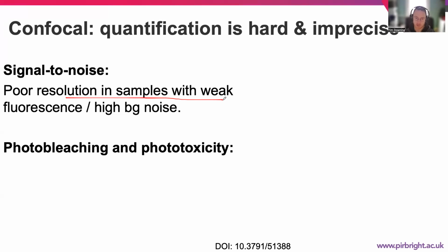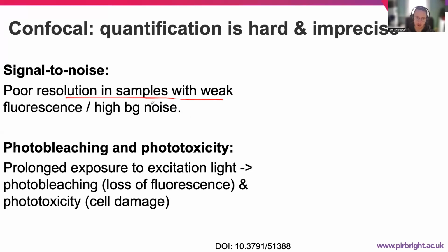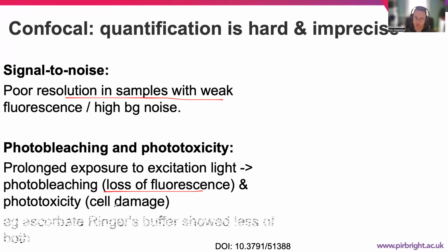So poor resolution samples, essentially dark images with high background noise, will be difficult to resolve. Photobleaching and also phototoxicity are also issues. Prolonged exposure to excitation light can mean that we get the loss of fluorescence known as photobleaching, or we get cell damage known as phototoxicity.